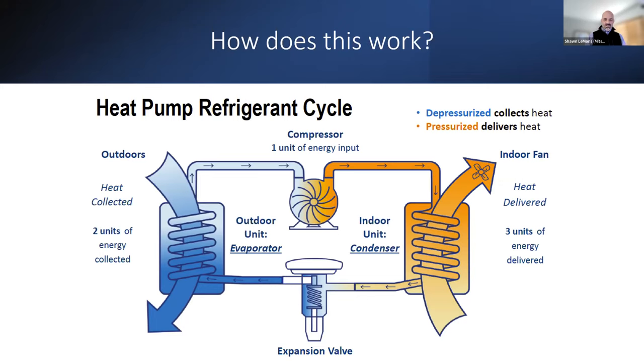What I want to point out with this slide is to demystify how a heat pump works real quick. The blue side is low pressure. The orange side is high pressure, if you will. The compressor in the middle pressurizes that refrigerant to deliver heat inside. And as that refrigerant goes back through that expansion valve, it depressurizes, cools off, and can now absorb the energy that's in the air on the outside, and then just gets recompressed and pushed back in. So it is a cycle that holds onto the refrigerant and just manages temperatures and pressures of that refrigerant to absorb heat from outside and deliver it inside. And by the way, this is how any air conditioner works in reverse in the summer. So that's as geeky as I'm going to get on that for today.